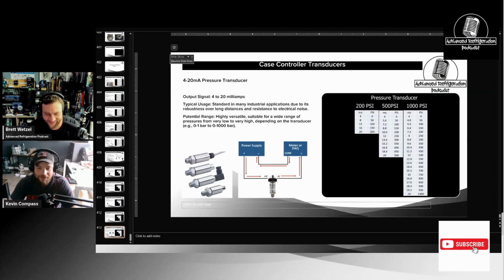So what you have to do is end up wiring your meter in series with this signal. On a Fluke meter, you have essentially 3 or 4 plugs on there if you have a proper meter that reads milliamps. You have a common plug generally that reads on all of them, then you have a milliamp plug. You're going to move your red lead of your meter into the milliamp plug. Now you're going to take your red lead and your black lead, and you're going to wire it in series with the voltage out going to the input. So where it says V minus on there, where he has it on the screen, and it goes to plus on there, you're going to wire your meter in series with this.